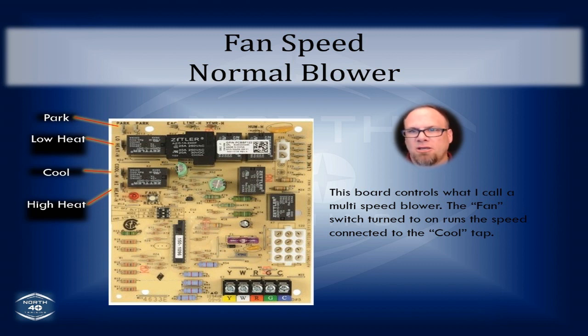So as you might guess, what I will do is I'll put my manometer in those two penetrations, the one before the blower, the one after the blower, and I will go from one fan speed, turn it on, write down the static measurement, pull it off and swap it out with another one on the cool, and then I will go to that one and write it down, and then I'll swap it out with a different one yet, and I'll go from one to the other on that cool terminal, turning the fan speed on, so that way it's very, very quick. I'm not using heat or I'm not using cool. I'm just looking at the raw values for the static and the ductwork. It's all I'm looking for, so I can properly set up that blower.